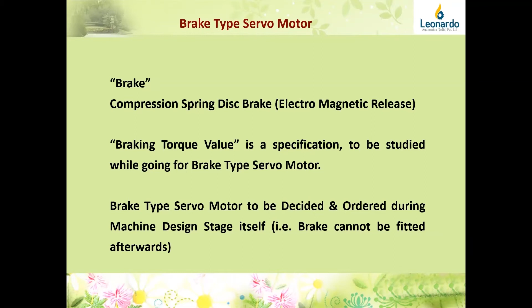If you are selecting a brake motor, the brake torque value is of significant importance, because if you are using a brake motor, probably it will be for a vertical slide, which should not come down automatically. Then the brake rating should be strong enough to prevent that automatic coming down. It will not be prevented if you are using a motor with inadequate brake rating. So this has to be understood and studied, and only then should you select the motor.